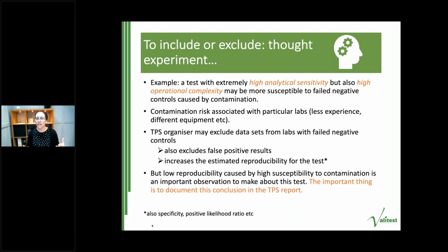You can probably imagine an example, perhaps a real-time PCR that's extremely sensitive, but very complicated because perhaps the matrix or the pathogen or the combination of the two means that you have to do a very complicated multi-step extraction process. So such a test that's highly sensitive but highly complex might be more susceptible to failed negative controls caused by contamination. So failed negative isolation controls caused by contamination. And that might vary a bit from lab to lab and be associated with labs which have less experience or which use particular equipment for the extraction.